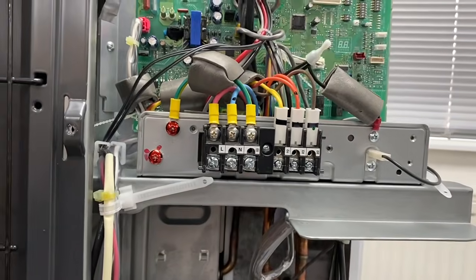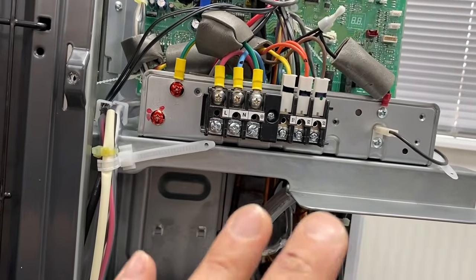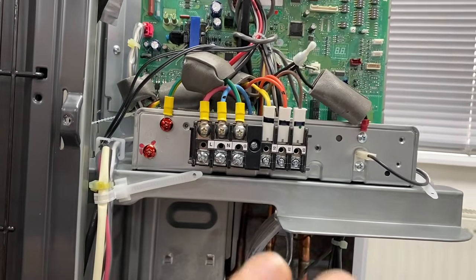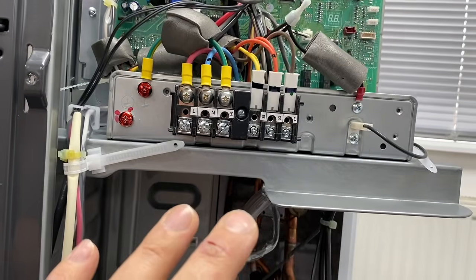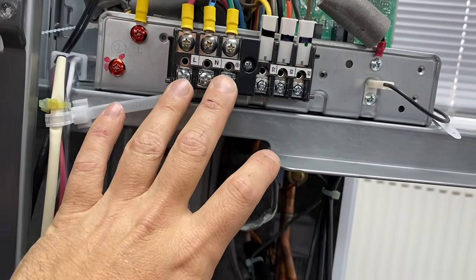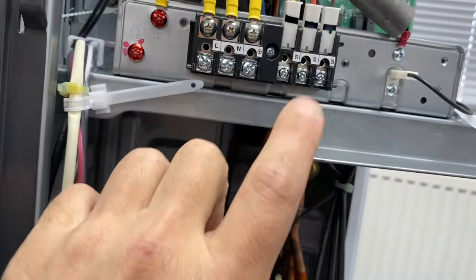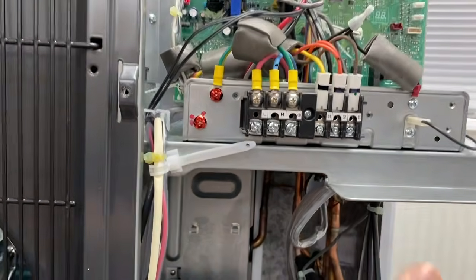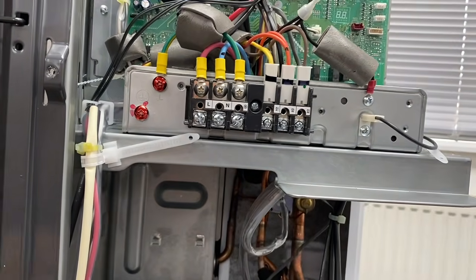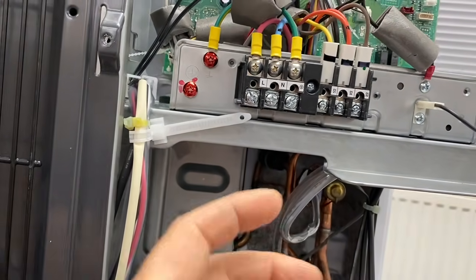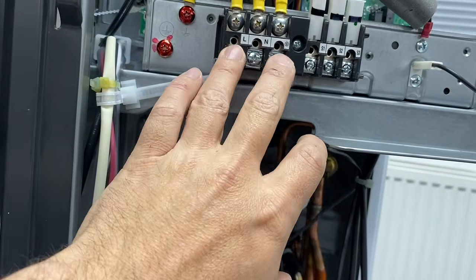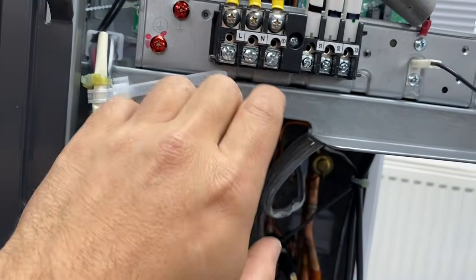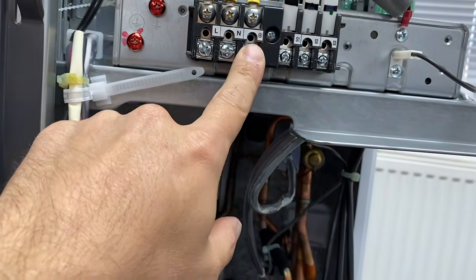Just here, for many of us, most of the connection points of the electricals will literally be at this point here. We've got your live feed in. This is going to come from your rotary isolator that will be on the outside. Depending on the size of the heat pump depends on how many amps you're going to need and what voltage is going to be required. Well, the voltage will stay the same, but it's the amperage. That will be connected here.